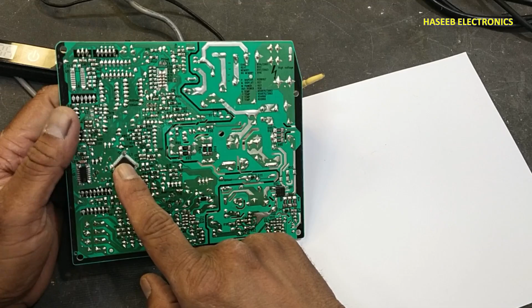With the thermostat switch in the refrigerator, when the temperature comes down, its contacts will make and it will start the compressor. Similarly here we don't have electromagnetic contacts or relay. The processor will use these optocouplers. These optocouplers will send commands by means of electronic signals. It is called a communication signal. It is bidirectional communication. Any time the processor wants to send a command to the outdoor unit, it will use one optocoupler and send the command. And if the outdoor unit sends any data or status command to this processor, it will receive it from this. And because all its items are electronically operated, if there is any malfunction, to protect from further damage, there is a special code that is displayed here.